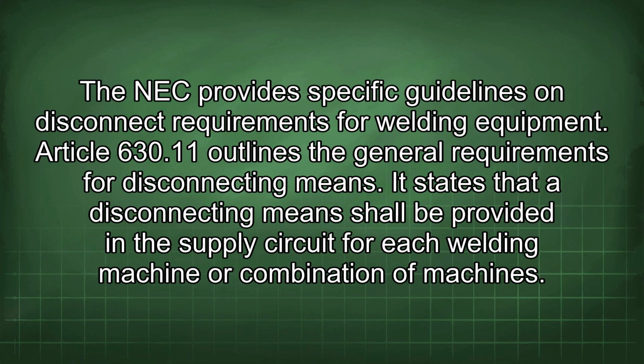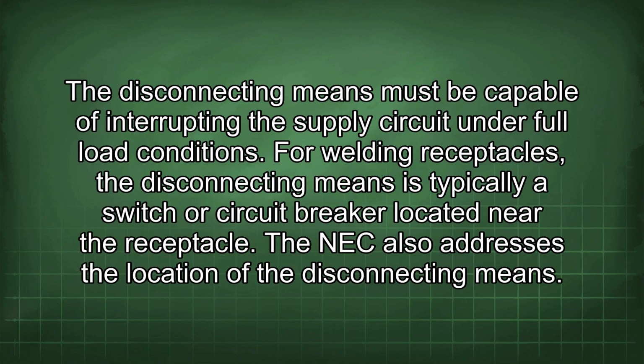The NEC provides specific guidelines on disconnect requirements for welding equipment. Article 630.11 outlines the general requirements for disconnecting means. It states that a disconnecting means shall be provided in the supply circuit for each welding machine or combination of machines. The disconnecting means must be capable of interrupting the supply circuit under full load conditions. For welding receptacles, the disconnecting means is typically a switch or circuit breaker located near the receptacle. The NEC also addresses the location of the disconnecting means.